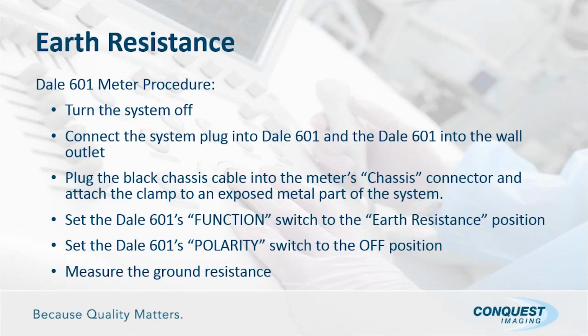For certain systems, certain manufacturers give you specific locations they want you to test from, and you'll see that on a slide coming up. So we'll talk more about that. Set the Dale 601's function switch to the earth resistance position, and then the polarity switch to the off position. Now this is an unusual position. This is a three-position rocker switch, and the off position is in the middle. So when you're in the middle, neither normal nor reversed, you can then measure the ground resistance.